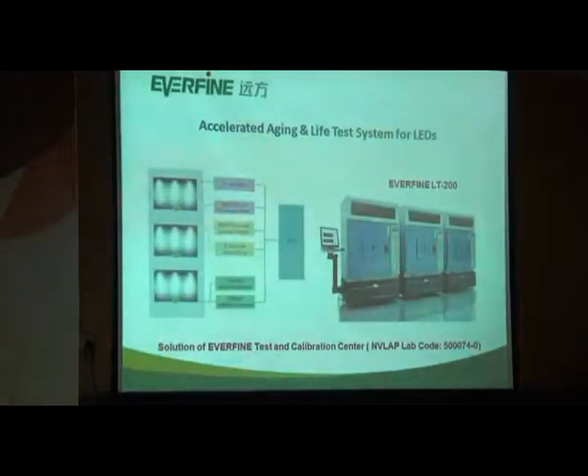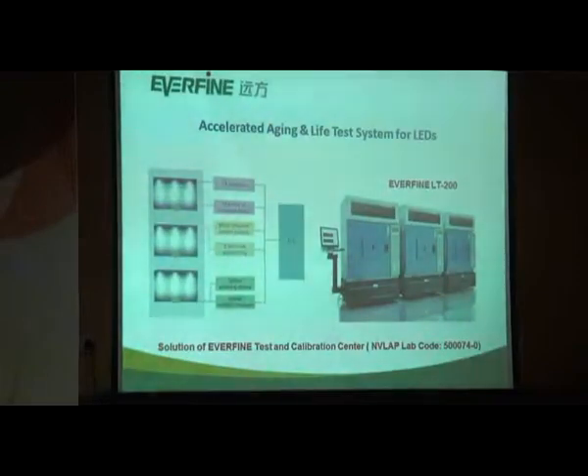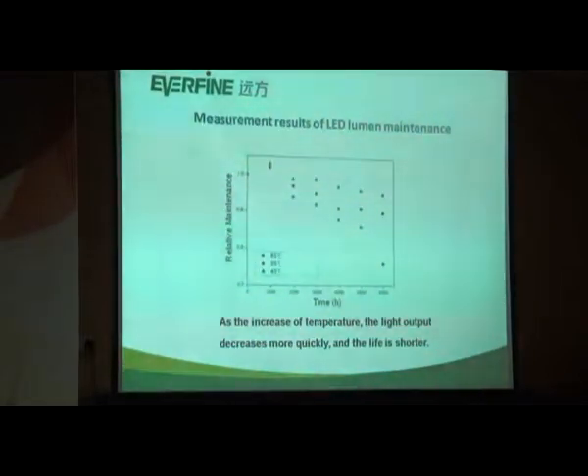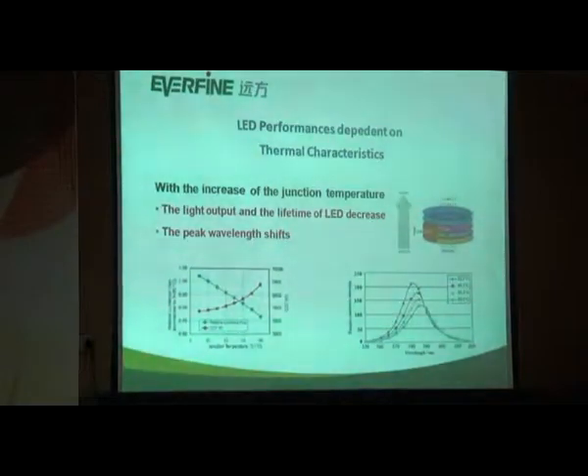As to the main instrument, this is the equipment produced by Everfine — this is also the solution of the Everfine Test and Calibration Center, which has been accredited by NVLAP, a national accreditation program of the US. This is the main result of lumen maintenance made by this equipment. From this figure, we can see that as temperature increases, the light output will decrease more quickly, which means lifetime is quite dependent on temperature.